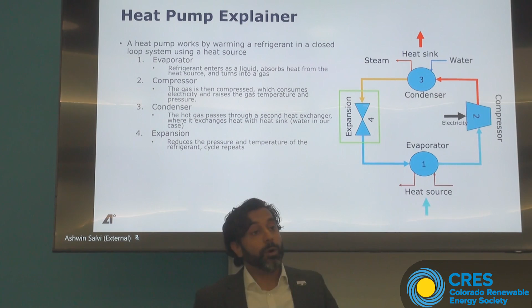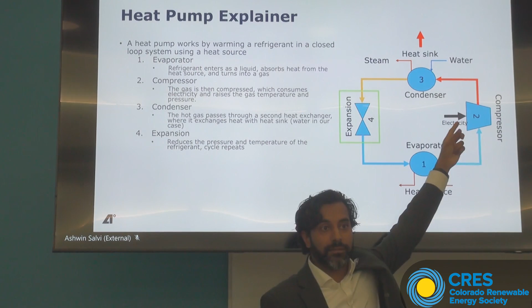So now the gas condenses, comes out as a medium temperature liquid out of the condenser, and the whole cycle repeats. This is how you're effectively just moving heat, absorbing it from one place and putting it somewhere else. That's why we can get efficiencies of over 100%, because we're not just converting 1 unit of electricity, thermalizing it into making heat. We're using 1 unit of electricity to drive a compressor, which then compresses and makes high temperature refrigerant.